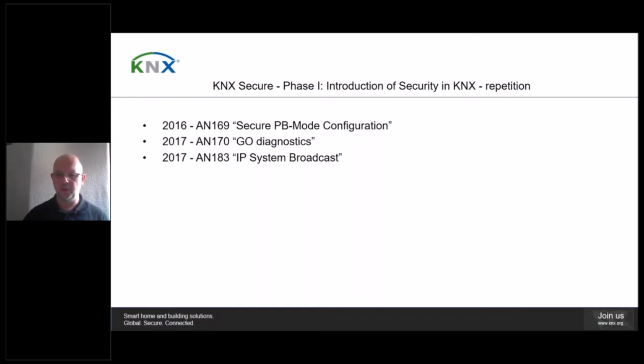ETS can only reach that new KNX IP device if it uses KNX IP routing and switches to the default KNX IP system setup multicast address. This can, for instance, not be done from the TP1 side of the KNX IP router. To circumvent this, an IP system broadcast has been introduced. The broadcast is known from KNX radio frequency, for instance. This is supported via the new KNX IP system broadcast frame, which looks like a classic routing frame, only with a dedicated service. Additionally, the domain address serial number write PDU has been extended to allow for secure transmission of the multicast address, security version, and backbone key.